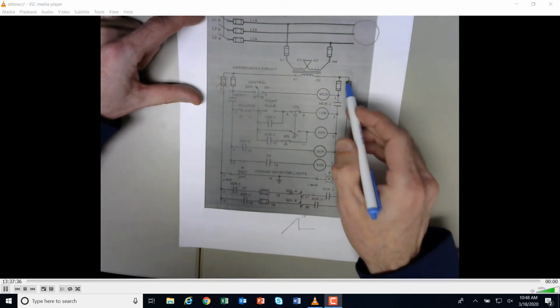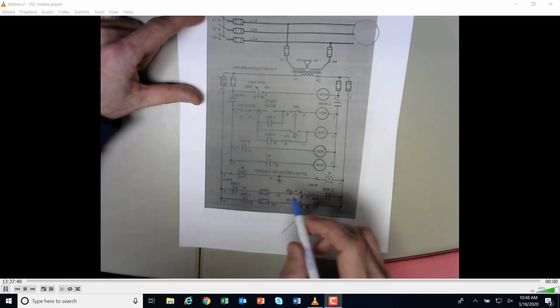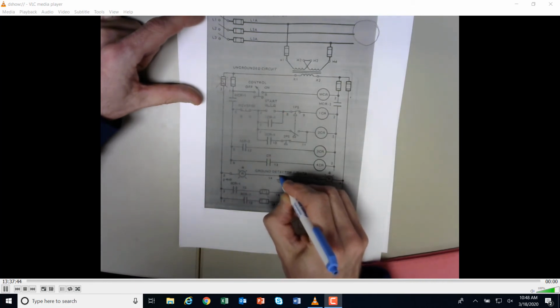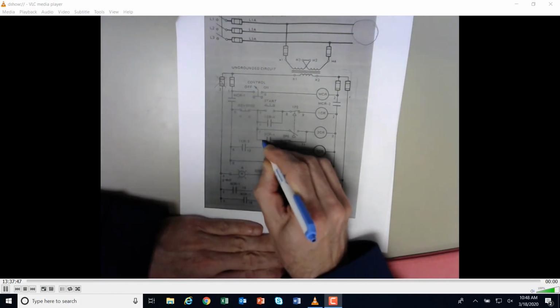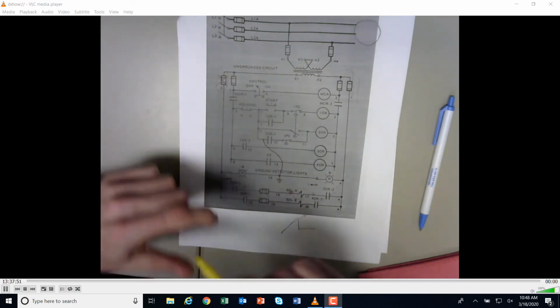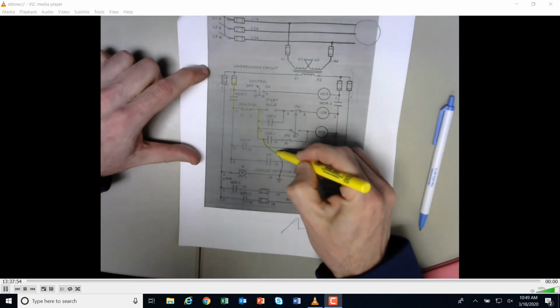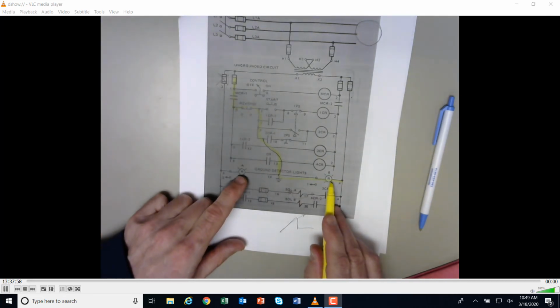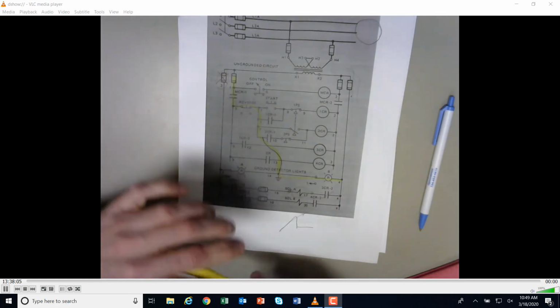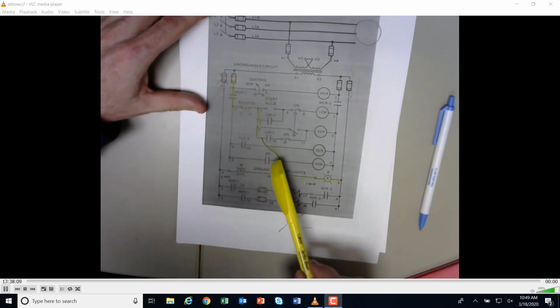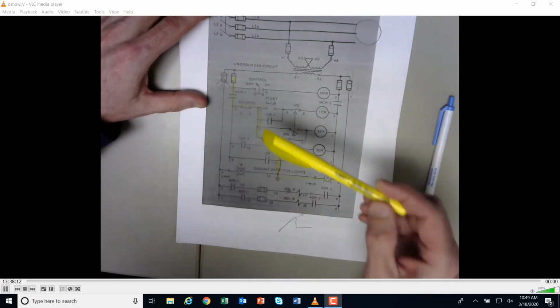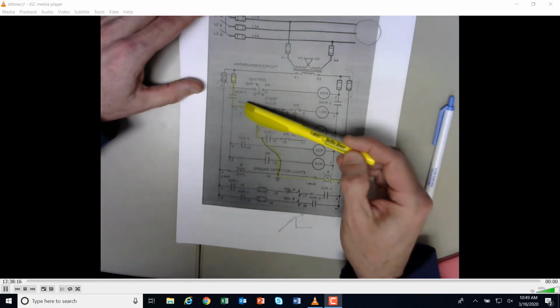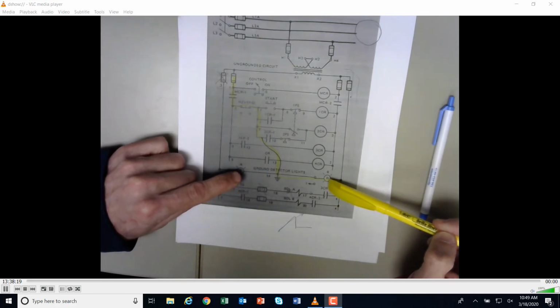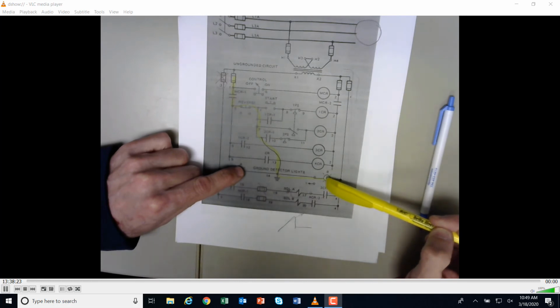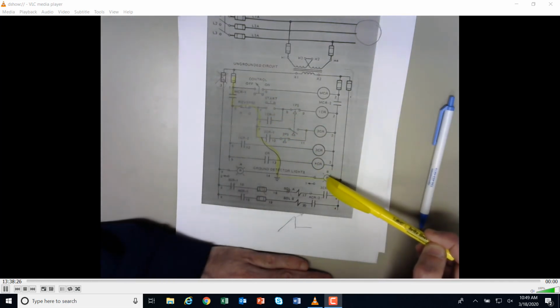And so what happens is this panel can have a fault, like we just showed here. For some reason, I had a fault up to here. Assuming that was on, I'm going to have flow of electricity to that light. And so instead of these being on just dimly, this light is going to go on. Based on my troubleshooting, this can help me troubleshoot where this circuit is. Now I can switch things off and on and start seeing if this light returns to normal, where it's half lit, or if I start pushing things, what's causing this light to come on bright.